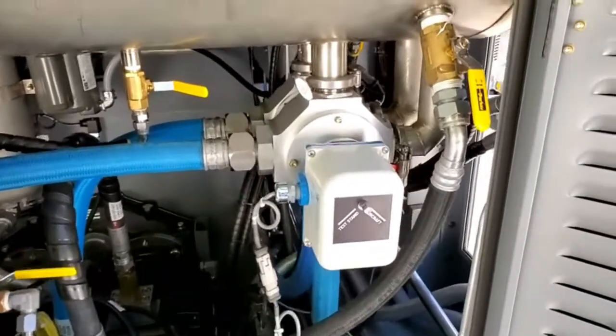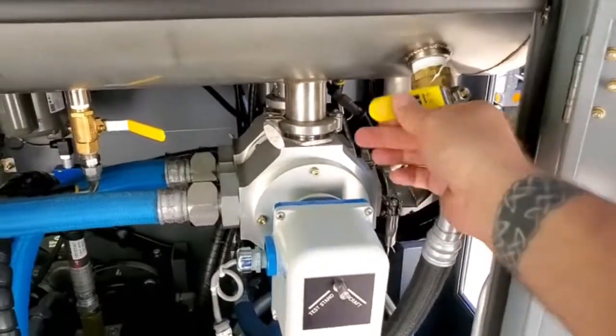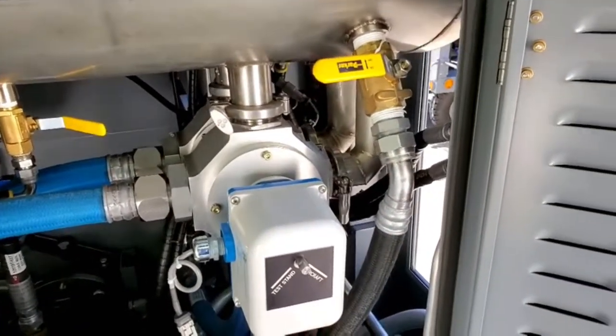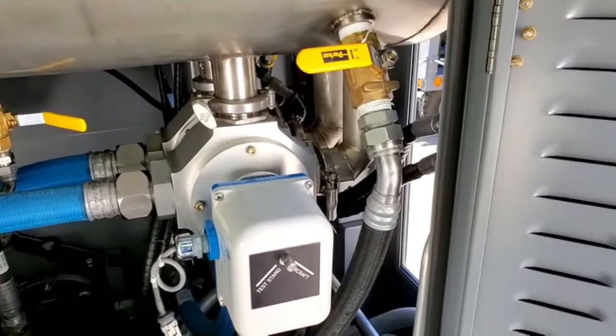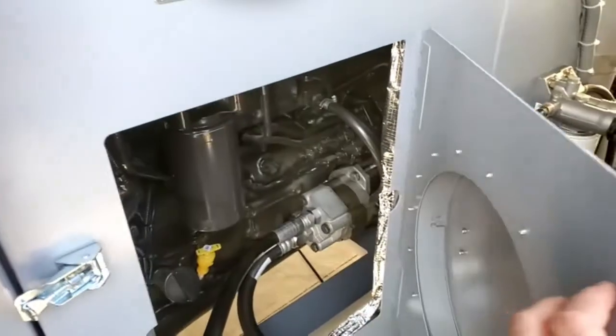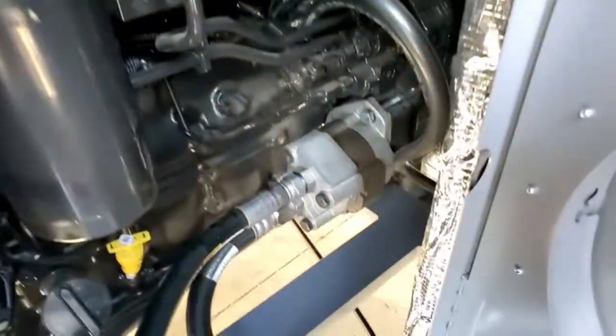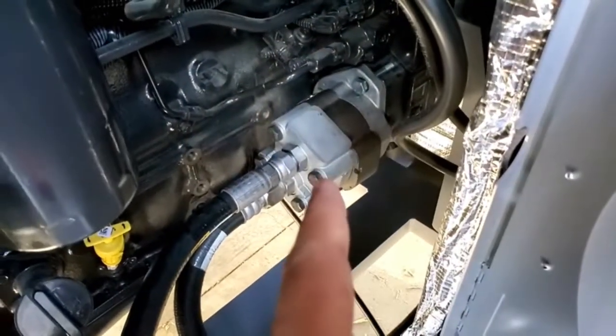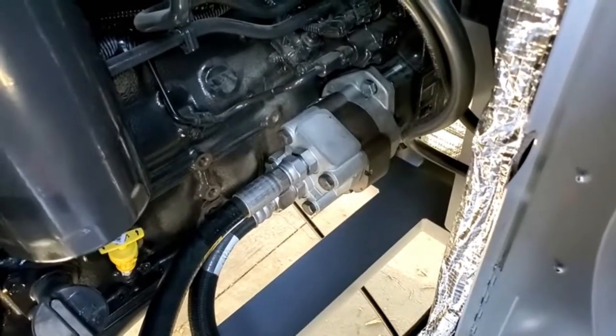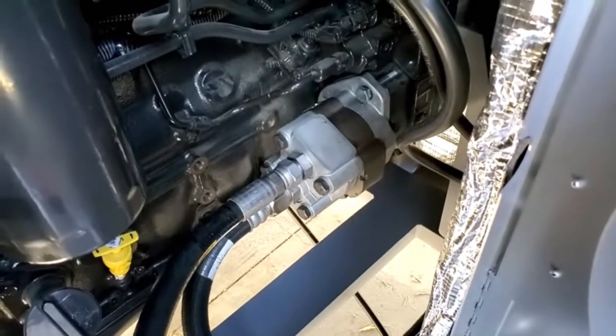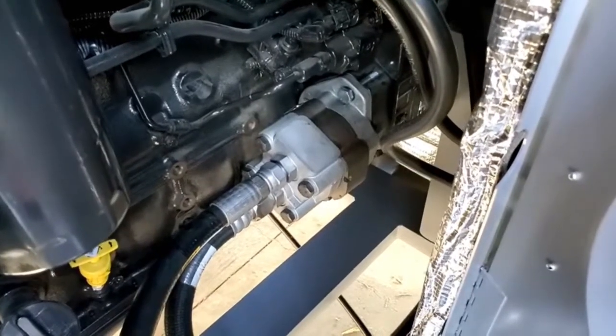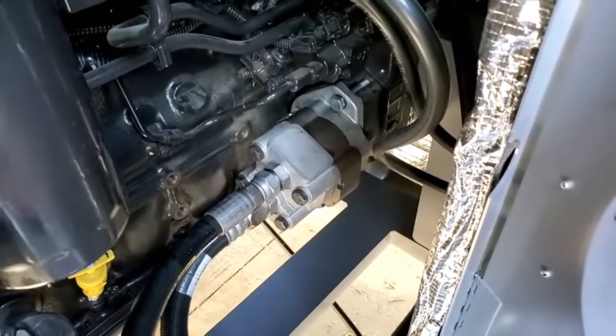If at any time on the diesel you're operating the engine, if you close this valve, you will cavitate and destroy the cooling system pump. The cooling system pump can be located on the front left access panel door. Open that and then open your engine access panel. And this here is your engine cooling pump. It's driven by the motor, so anytime the motor's operating, that pump is moving. It must have hydraulic fluid flow to it at all times.